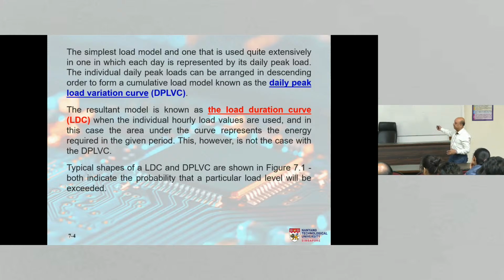But if you look at the load duration curve, because it deals with hourly loads, the area under this curve is actually the energy required by the load. Because it deals with hourly values, you will get megawatt hours, kilowatt hours, gigawatt hours directly. Whereas if you use the daily peak load curve, it's not going to give you exactly the energy. The load is on a daily basis, so it gives you megawatt days, gigawatt days, not megawatt hours, right? So that's not a true representation of the energy required by the load. That's why whenever energy calculations are needed, we use the load duration curve. But if you are only after the loss of load expectation, you could use either. And I'll show you the use of both of them, hopefully, one through an exercise and the other through an example, okay?